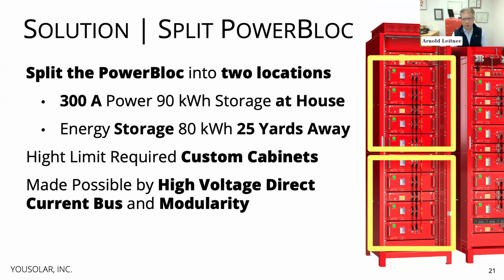Because the PowerBloc is modular and connected through a 400-volt energy bus, we can put things in separate locations. We can separate some of the storage from the rest of the PowerBloc, and that's what we did. In this case, only 25 yards away. We have another house, not shown today, where the storage and power cabinets are separated by 150 yards. That would be completely impossible with the current 50-volt systems on the market. It's only possible at the high electric potential of 400 volts, where losses are about 60 times lower than over commensurate wire at 50 volts.